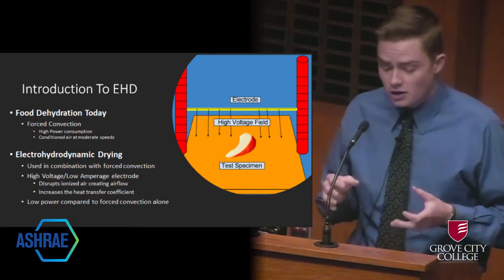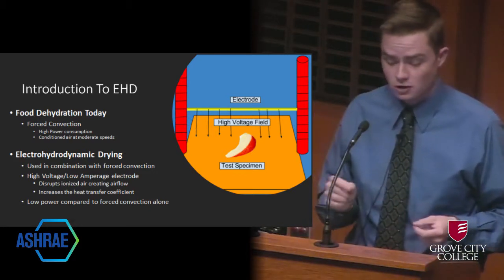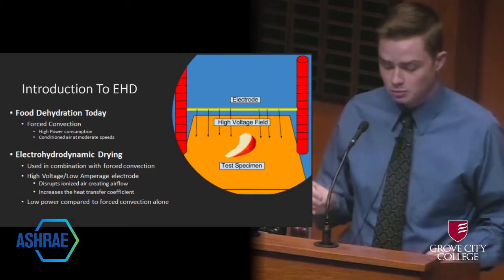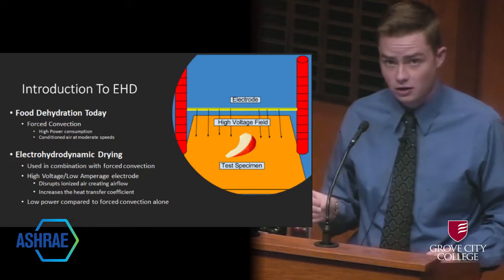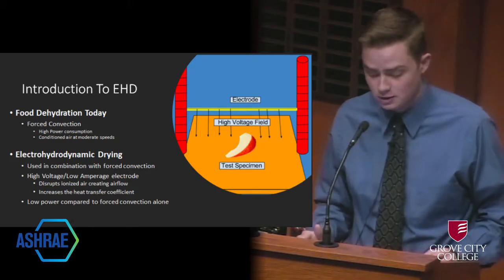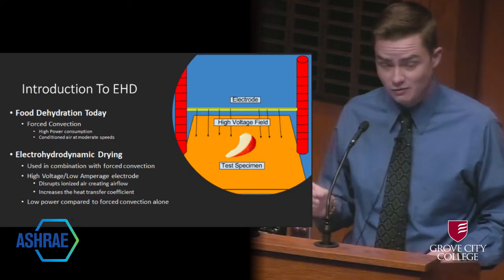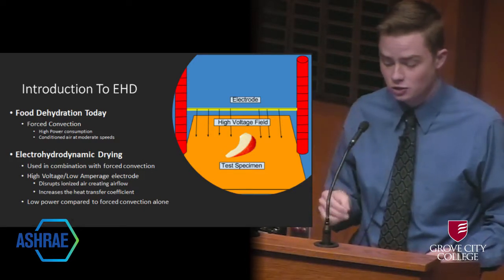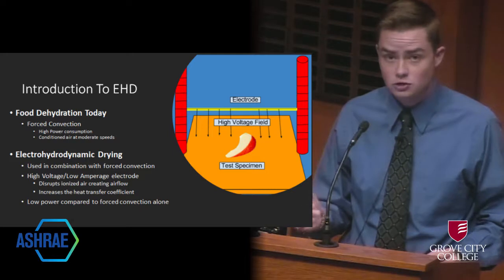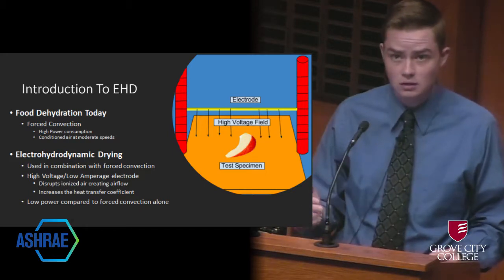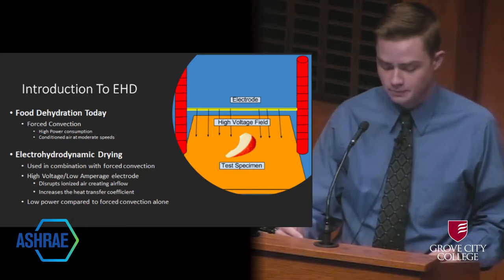Even though this is a very high voltage, the electrode carries a very low current. The power supplied to the electrode has a current cutoff actually of 300 microamps. Due to the system having a high voltage but very low current, the total power consumed is under 2 watts of energy for a normal test.